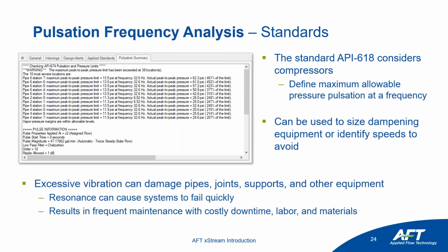And the main concern, especially with pulsation, is that the time to failure can be very short because you're constantly inputting energy. Again, think of the swing. If you're perfectly timing your push, you're compounding all that energy, and that leads to a very short time to failure.